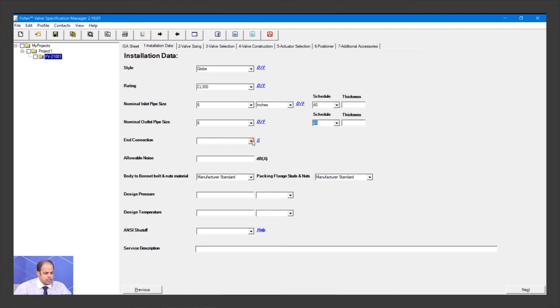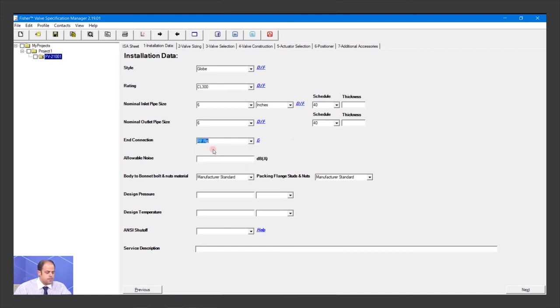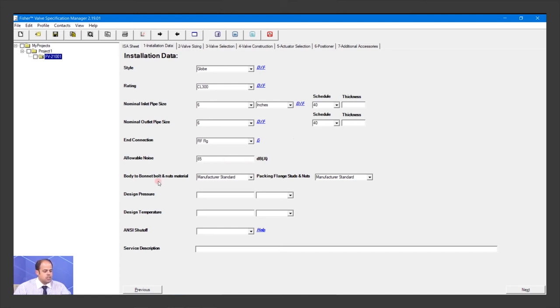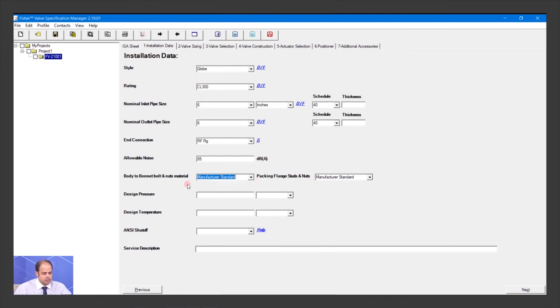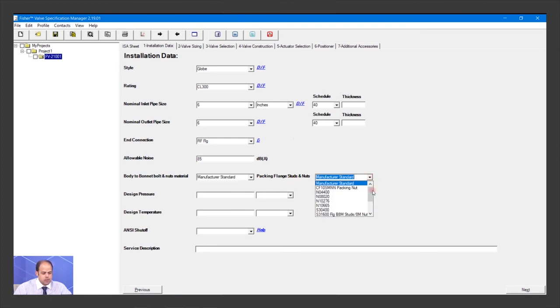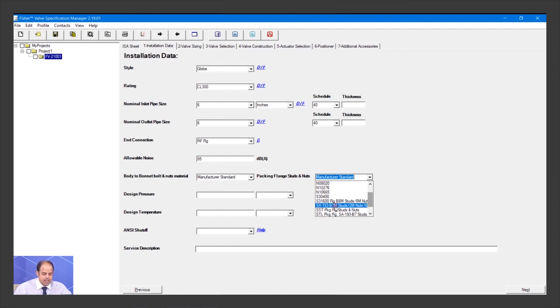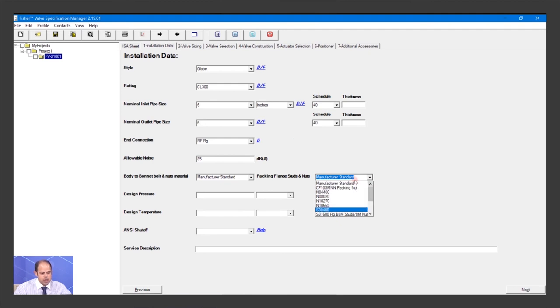The end connection is raised face flange. Maximum allowable noise is 85. For body and bonnet, you can choose anything or put it to manufacturer standard. For studs and nuts, you can choose ASTM A193 or other specifications, but I recommend manufacturer standard.